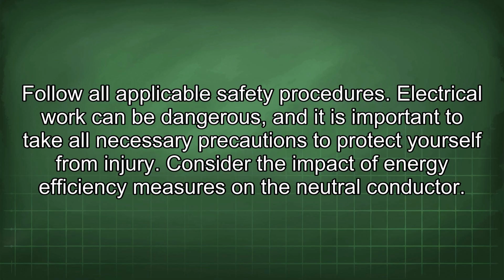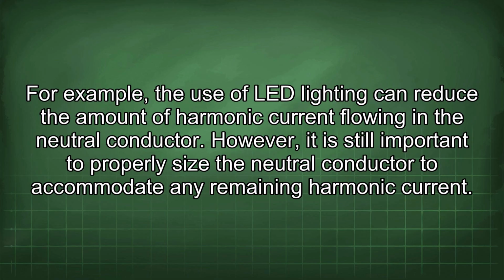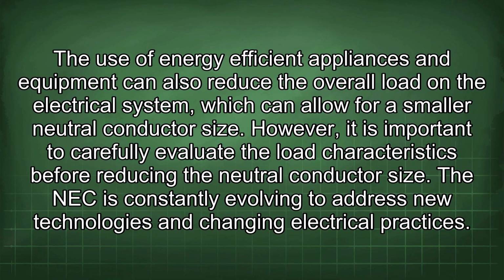Consider the impact of energy efficiency measures on the neutral conductor. For example, the use of LED lighting can reduce the amount of harmonic current flowing in the neutral conductor. However, it is still important to properly size the neutral conductor to accommodate any remaining harmonic current. The use of energy-efficient appliances and equipment can also reduce the overall load in the electrical system, which can allow for a smaller neutral conductor size. However, it is important to carefully evaluate the load characteristics before reducing the neutral conductor size.